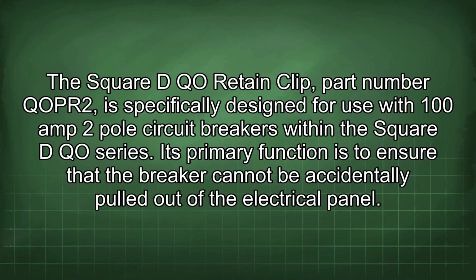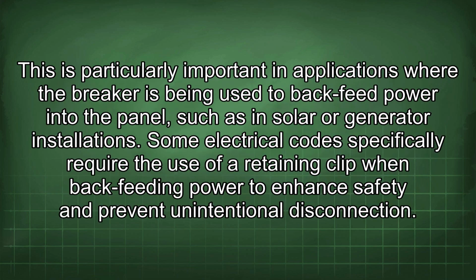The Square D QO retain clip, part number QOPR2, is specifically designed for use with 100 amp 2-pole circuit breakers within the Square D QO series. Its primary function is to ensure that the breaker cannot be accidentally pulled out of the electrical panel. This is particularly important in applications where the breaker is being used to backfeed power into the panel, such as in solar or generator installations.